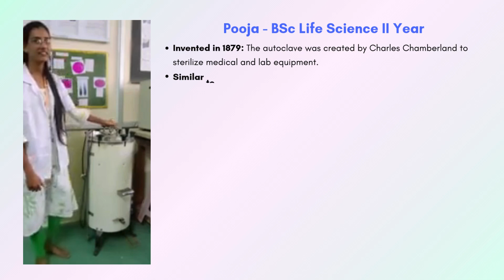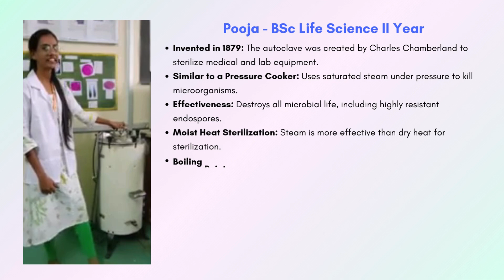Pooja, BSc Life Science, second year, autoclave. Autoclave was invented by Charles Chamberland in 1879. The autoclave is a sealed device similar to a pressure cooker that kills all microorganisms using saturated steam under pressure. The use of moist heat kills all microorganisms, including the highly resistant endospores.